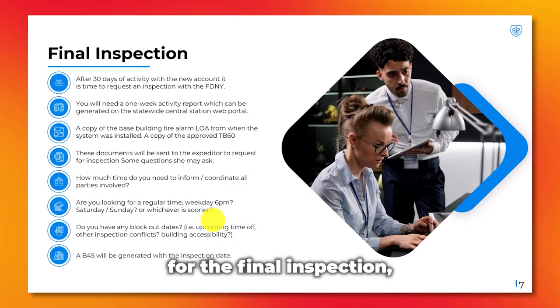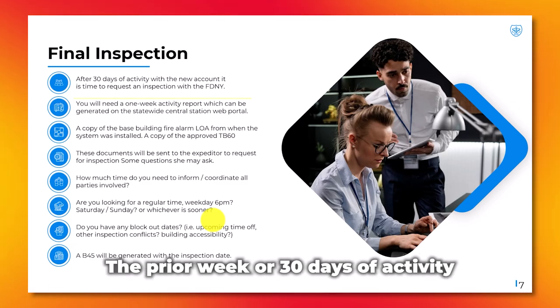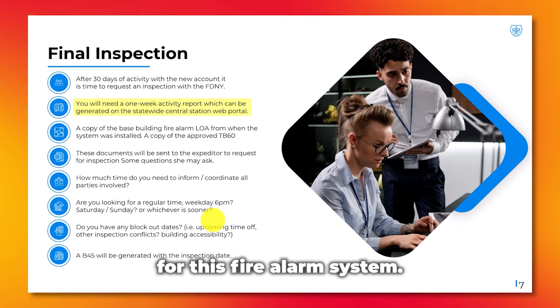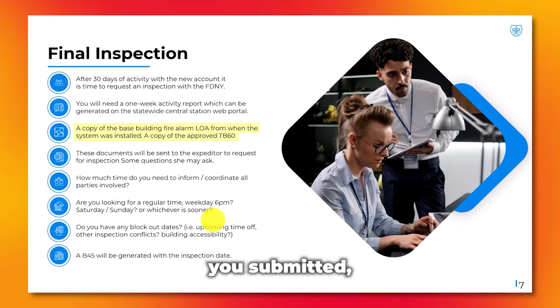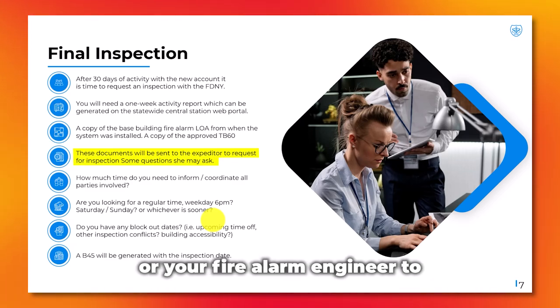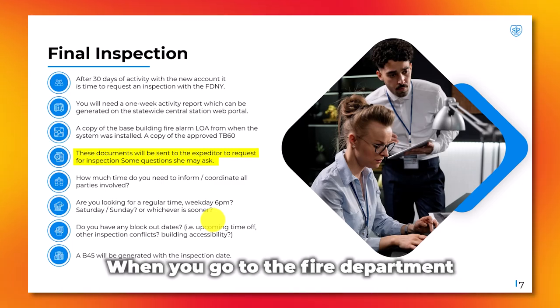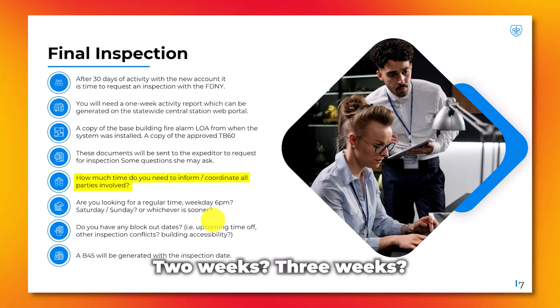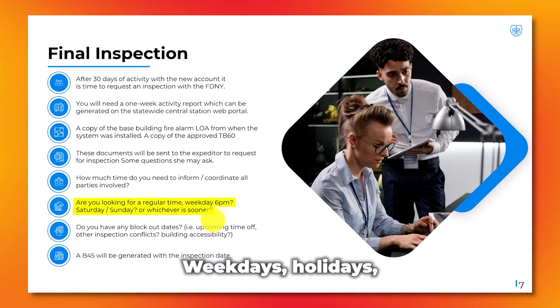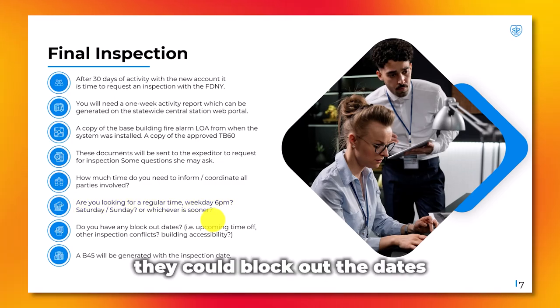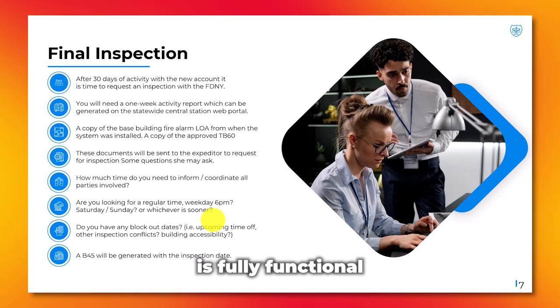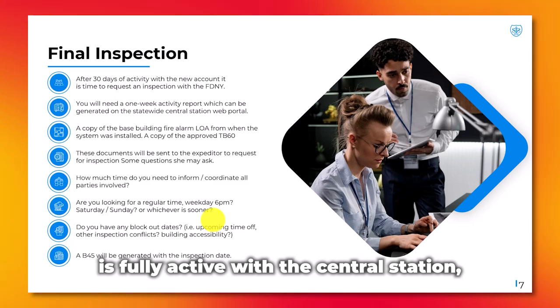Once you're scheduled for the final inspection, you'll need an activity report from the prior week or 30 days of activity for the fire alarm system, a copy of the base building fire alarm letter of approval, and a copy of the approved TB-60 you submitted. Send these documents to your expediter or fire alarm engineer, or submit them yourself to the fire department. Specify your time frame for inspection — two weeks, three weeks, weekdays, after hours, whatever you need — so they can block out dates and give you an inspection. Make sure all devices are tested, the system is fully functional, and your monitoring account is fully active. You'll then get a B-45 with the inspector's name and the date and time.